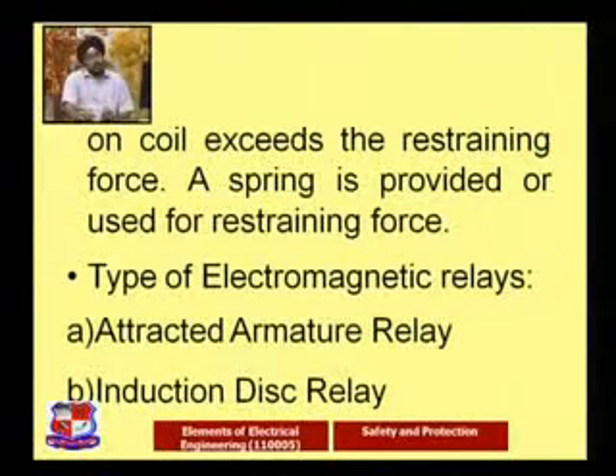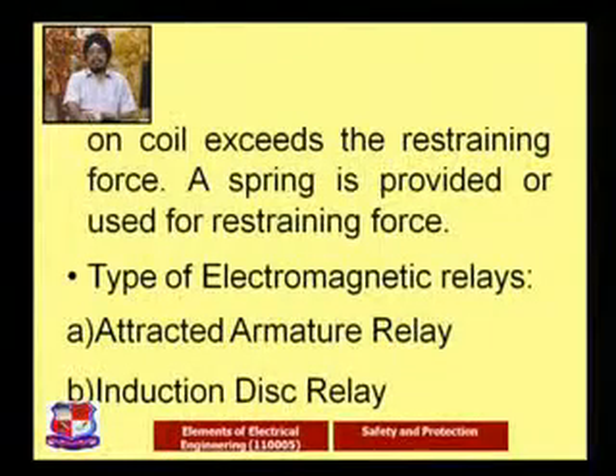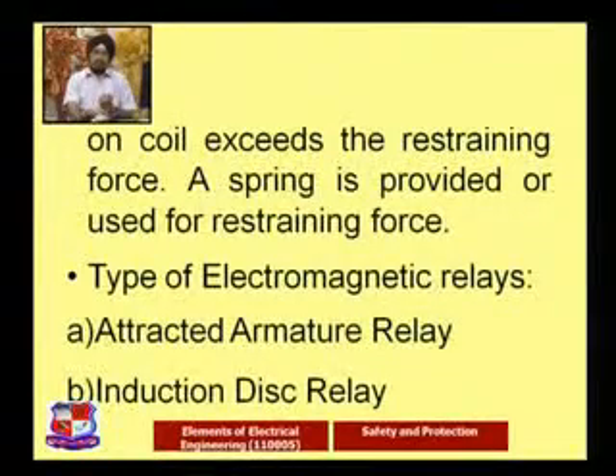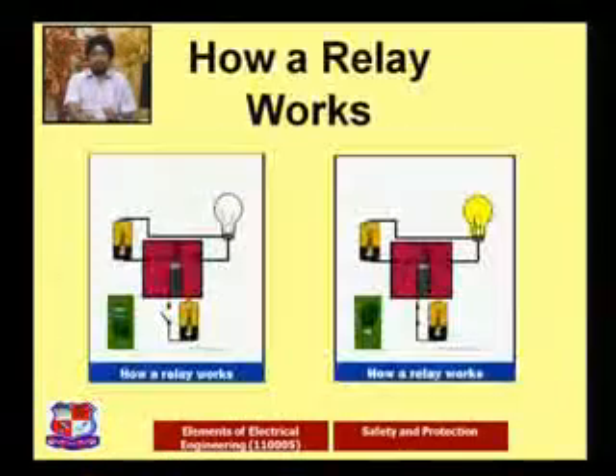Types of relays. Now there are two major divisions of relay with respect to this subject: the attracted armature relay, and the second one is the induction disc type relay. In the attracted armature relay, the armature is going to be attracted when energy is flowing. In the induction disc relay, the disc is going to rotate when the energy flows through it. That is the major classification of the types of relays.